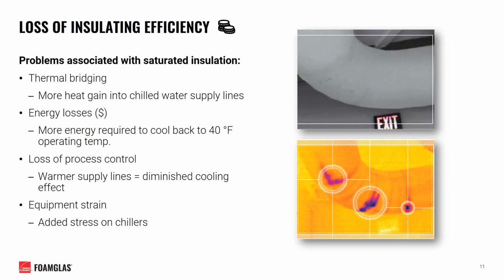One more consequence of excessive condensation taking place within your insulation involves the loss of that insulation's efficiency. If the wrong insulation material is chosen, it actually can absorb and retain any moisture from condensation occurring. It's widely known in the industry that insulation becomes much less effective when it's allowed to become saturated with water. This can lead to thermal bridging, allowing more heat gain back into your chilled water supply lines, which will lead to energy losses and increased costs, requiring more energy to cool those pipes back down to that 40-degree operating temperature.